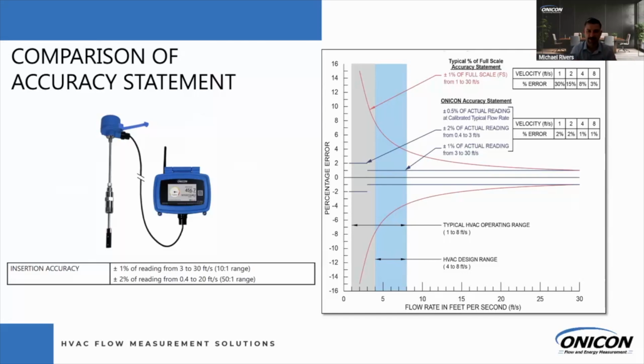So to do an example to hit this idea home, you have two flow meters that both could read 0 to 5,000, but you're trying to measure 300. Well, a 1% of full scale device is going to be 1% of 5,000, or plus or minus 50. All of ONICON's flow meters are percentage of reading devices, or 1% of the 300, or plus or minus 3. At initial look, both 1%, but they mean something much different.